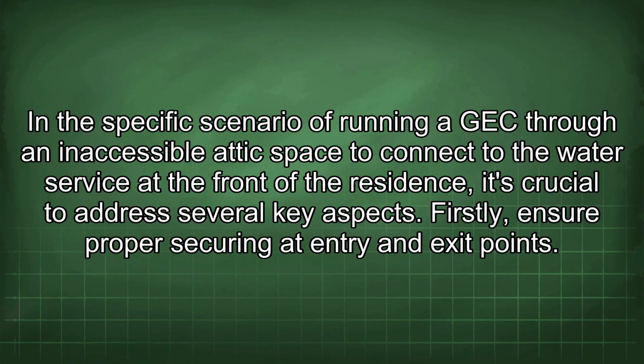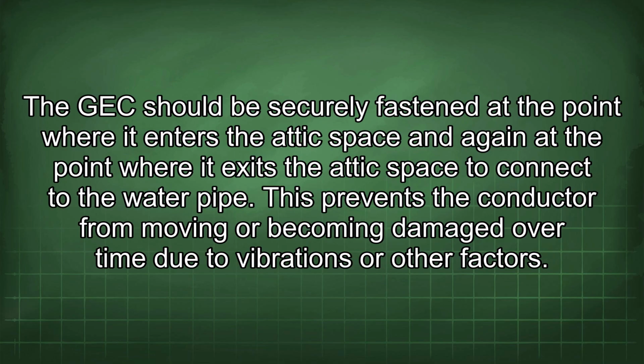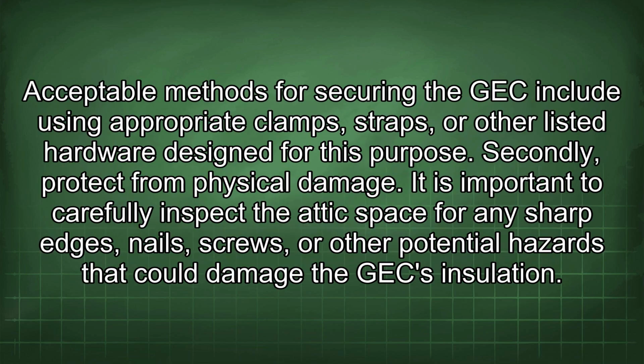In the specific scenario of running a GEC through an inaccessible attic space to connect to the water service at the front of the residence, it's crucial to address several key aspects. Firstly, ensure proper securing at entry and exit points. The GEC should be securely fastened at the point where it enters the attic space and again at the point where it exits the attic space to connect to the water pipe. This prevents the conductor from moving or becoming damaged over time due to vibrations or other factors. Acceptable methods for securing the GEC include using appropriate clamps, straps, or other listed hardware designed for this purpose.